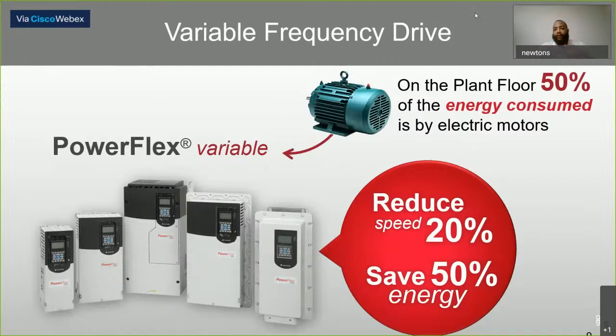So going back, over 50% of energy is consumed by electric motors. The neat thing about variable frequency drives is that you're able to control the speed of your motor with this technology, from very low speed, 1% speed, to 100% speed, and even in some cases over 100% speed. So you can control the speed and torque of your motor using a variable frequency drive. And if you reduce the speed of your motor by 20%, you'll save 50% energy.